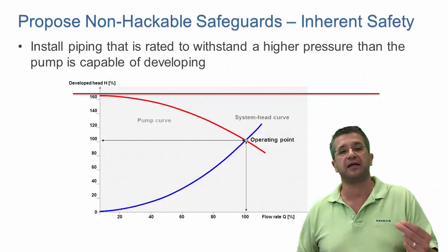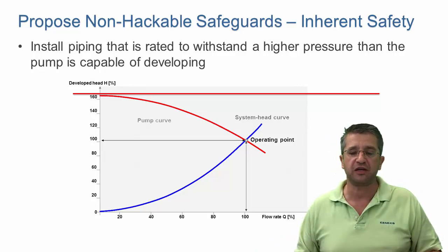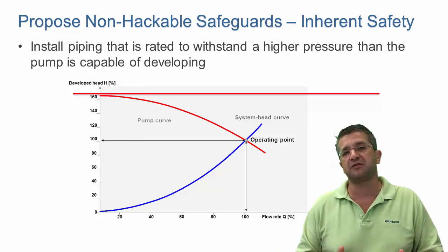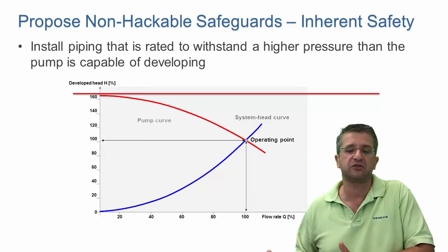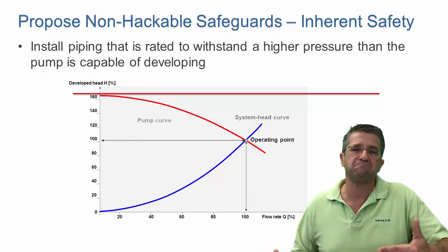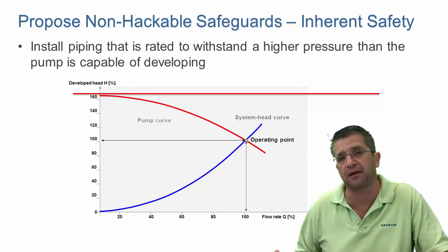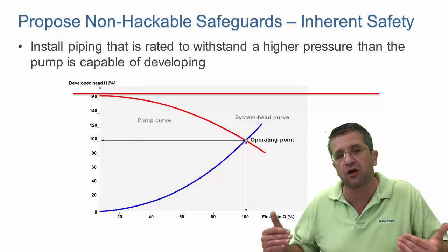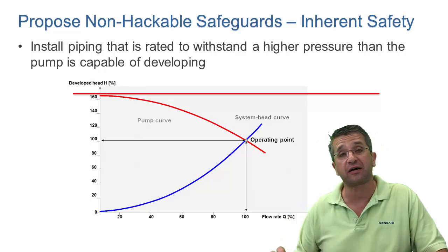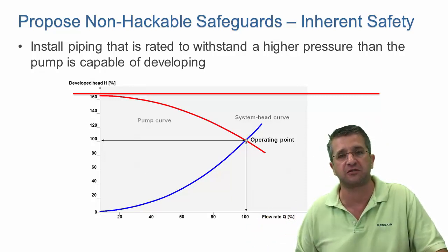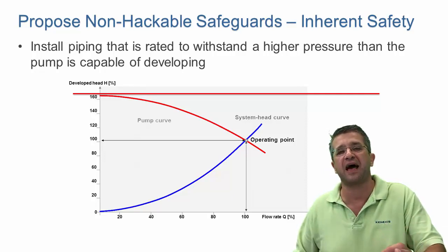The one thing that is absolutely inexcusable is that you could have made the design inherently safe against this scenario. What you see here is a typical pump curve of a centrifugal pump. As flow rate increases, discharge pressure decreases. If you go all the way to zero flow, there's a maximum head — a maximum pressure — that this pump can develop. All you need to do is make sure that the discharge piping is rated to withstand that much pressure, and this loss of containment explosion and fire cannot happen. We're only talking about a couple of meters of piping between the pump and the isolation valve.